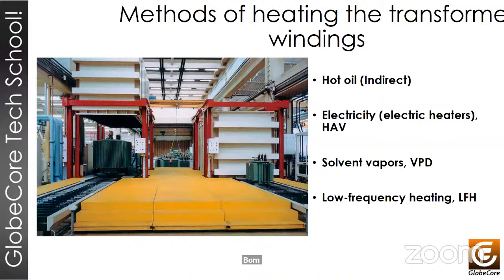Now, low-frequency heating. This method consists of heating the actual winding by applying low-frequency currents to the winding itself. The advantage of this method is that the actual winding is directly heated, which explicitly affects the energy efficiency and the cost effectiveness, which is something that all of you are interested in.